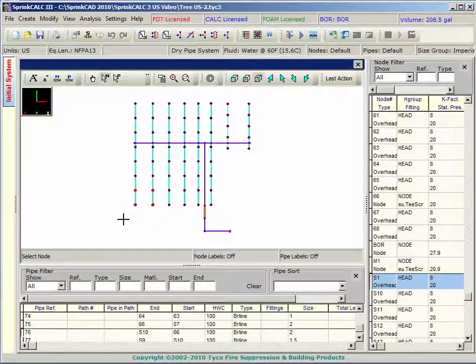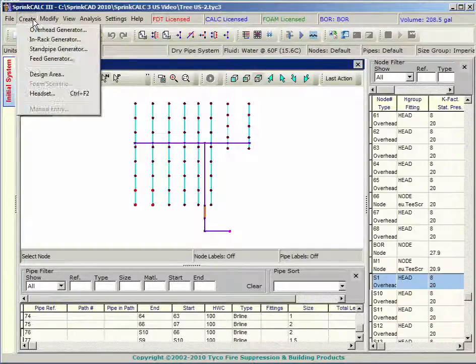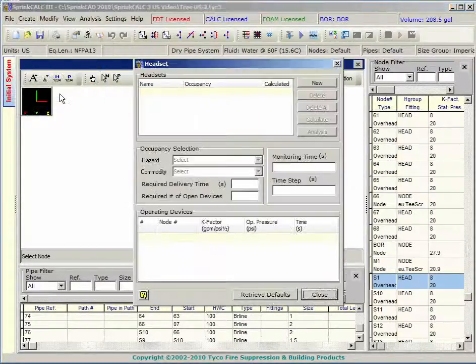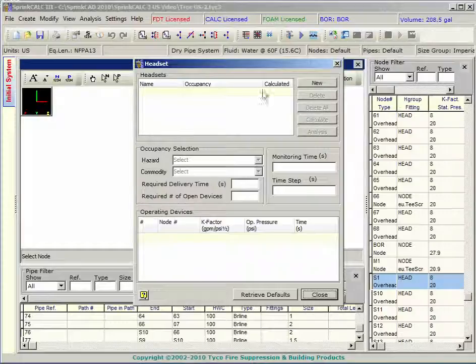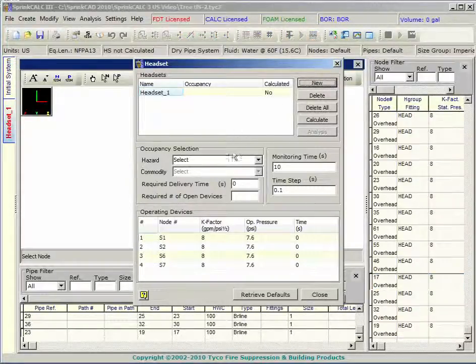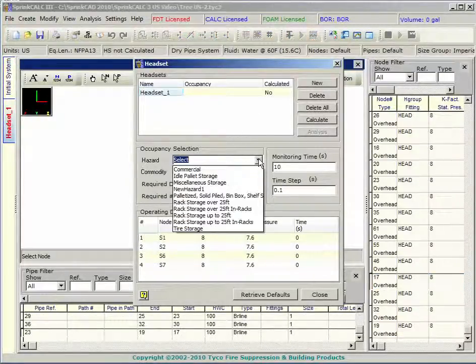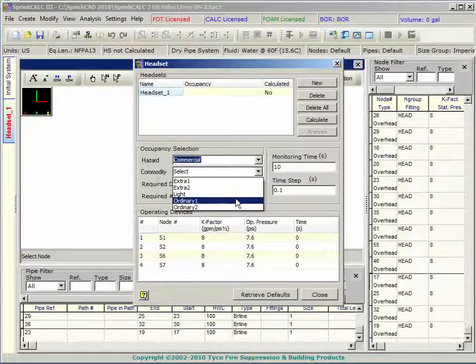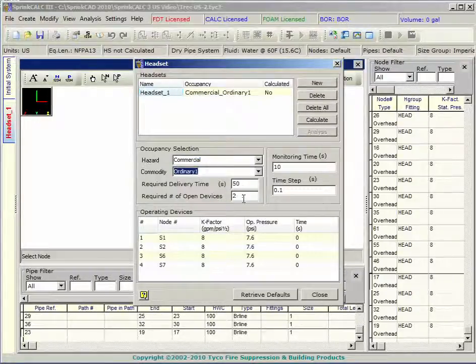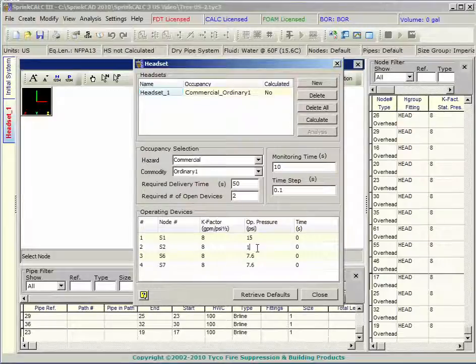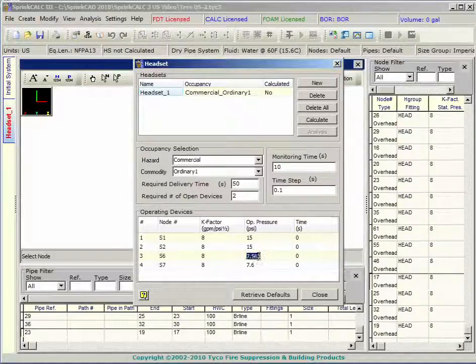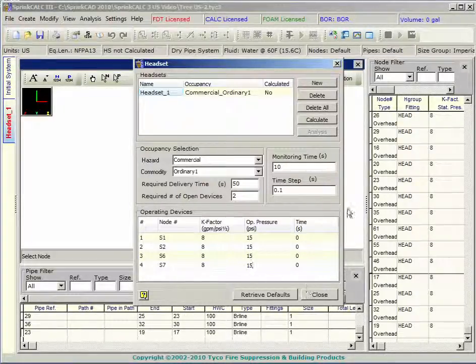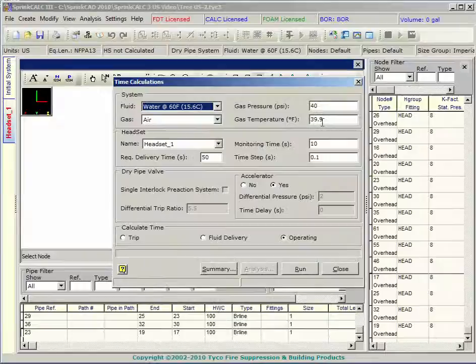You identify a headset, which is a collection of heads that will open in the event of a fire. In this example, 4 sprinklers are selected for the calculation. Select the hazard and commodity to get the delivery time requirements of NFPA 13. Specify the operating pressure for the minimum density for the hazard.